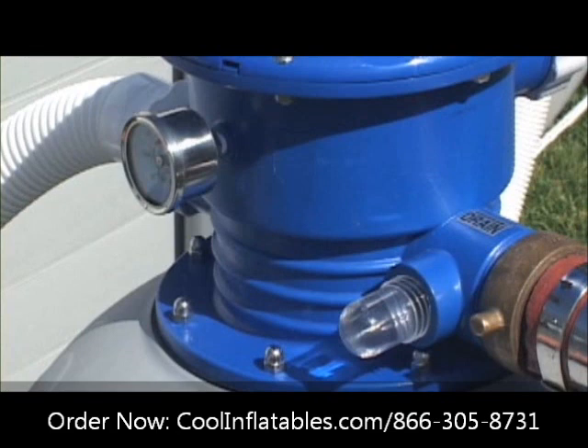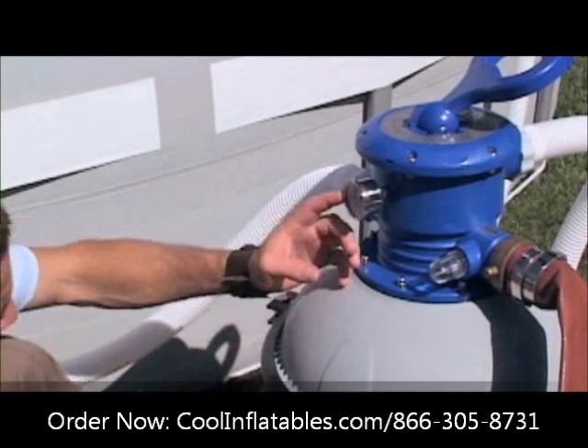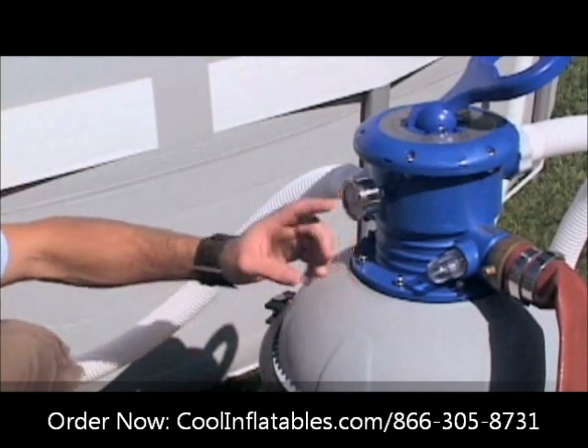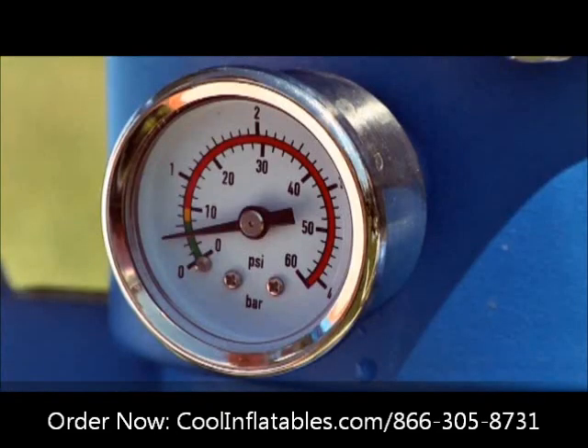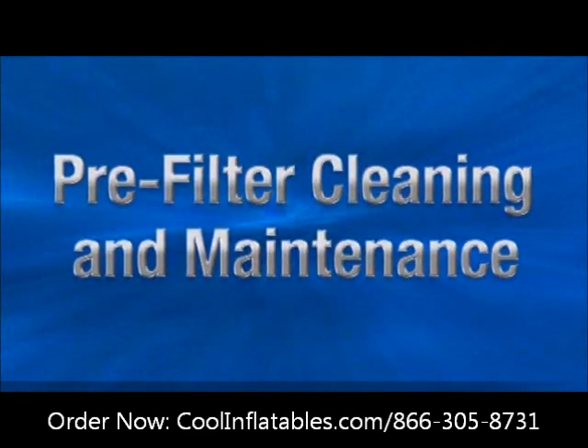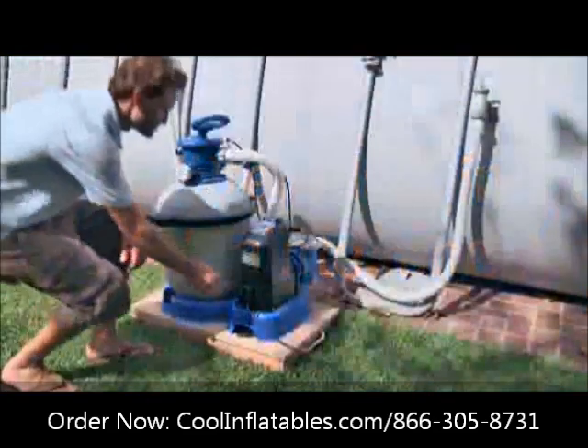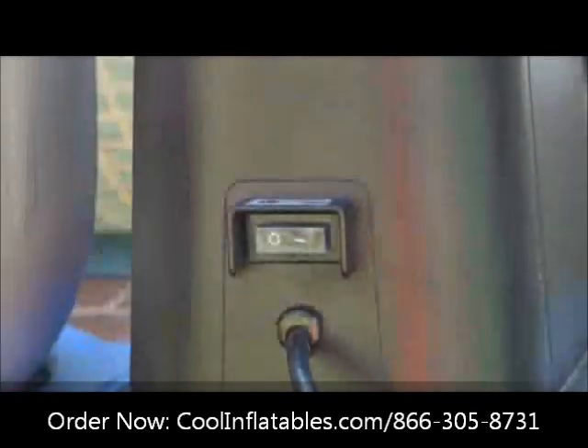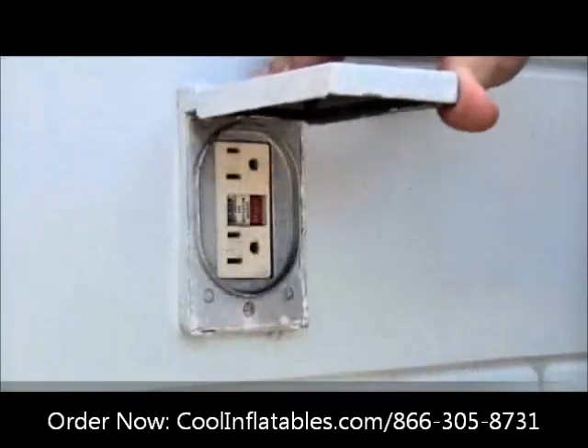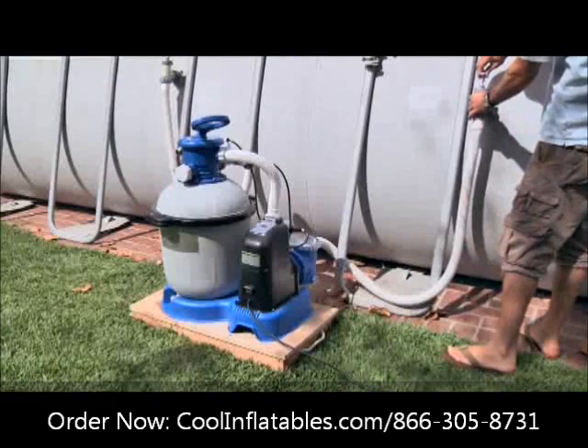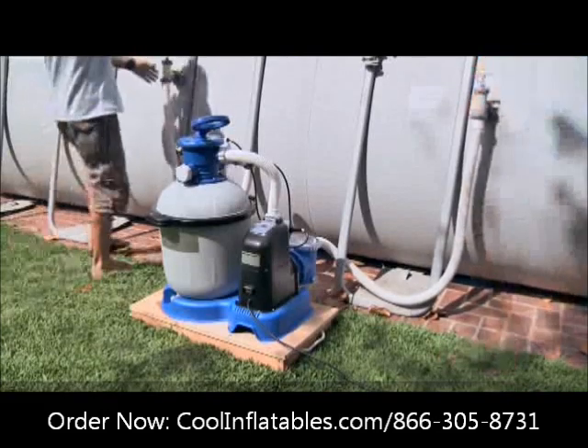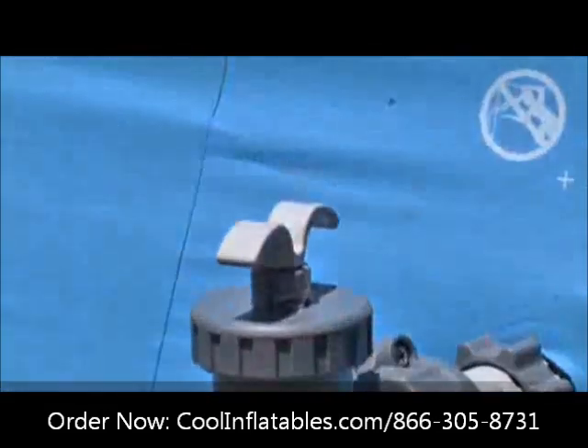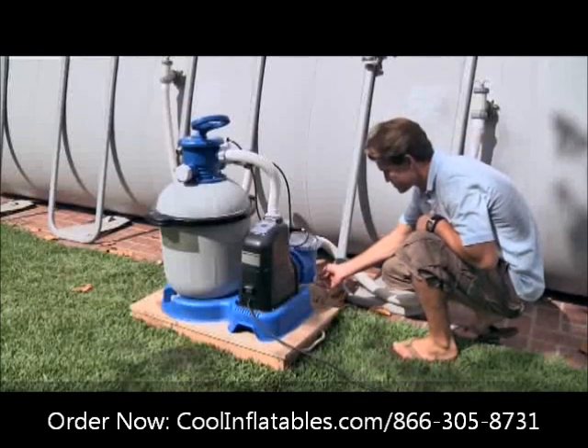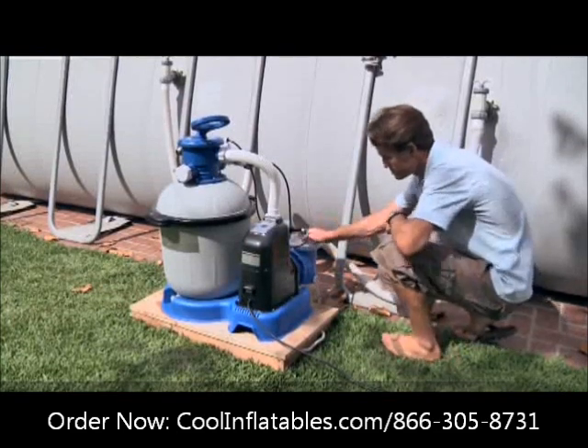When the sand has been washed clean, record the pressure gauge reading. As dirt accumulates in the sand, the pressure will rise. When it reaches the yellow zone, backwashing will be necessary. Before cleaning and maintenance, turn the pump off and disconnect the power cord. Close both plunger valves. Release the pressure by opening the sediment valve on the lower side of the filter housing.